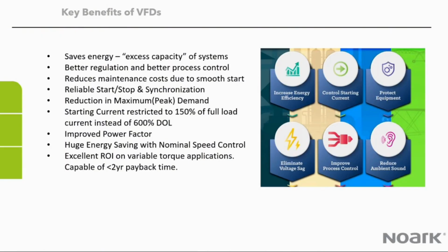Improved power factor because the drive is between the line and the motor. The motor may have a certain power factor, the drive has its own, which is up in the upper 90 percentile. So great use of power factor savings. And excellent ROI on variable torque applications, which Jason will talk about in a little bit, capable of less than 2 years payback. So a great way to utilize VFDs.